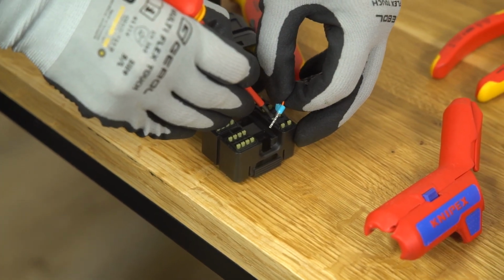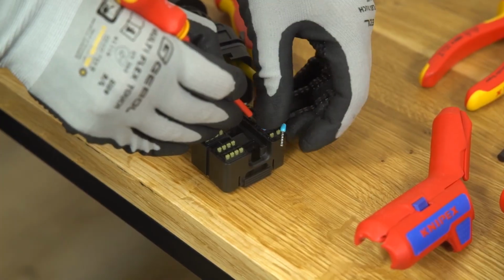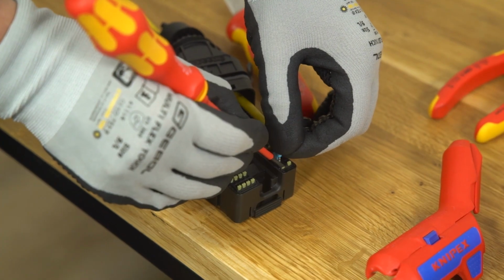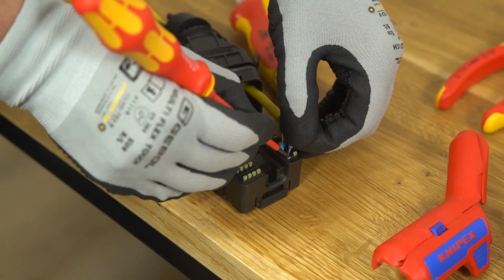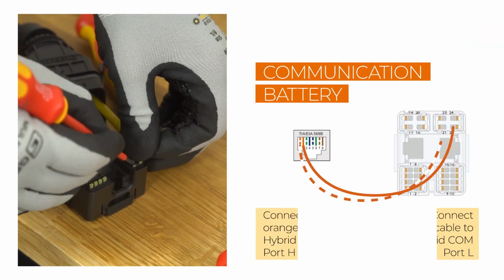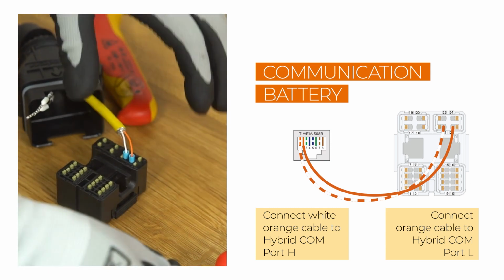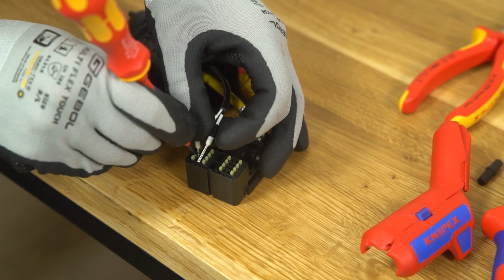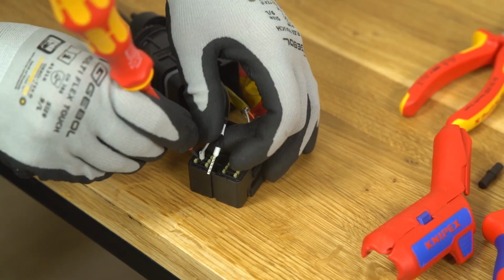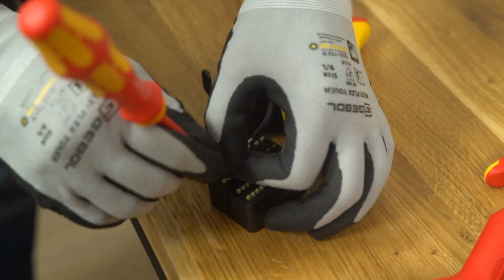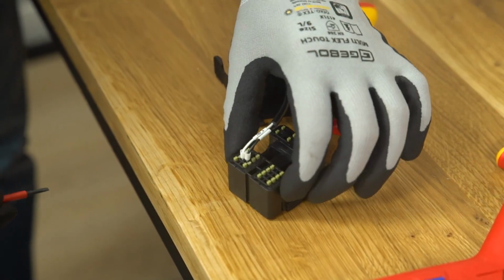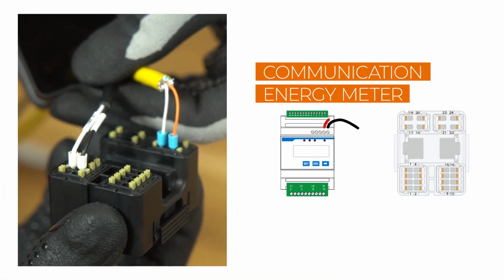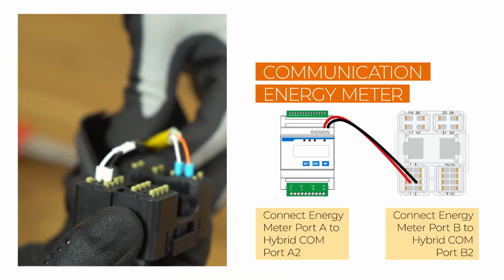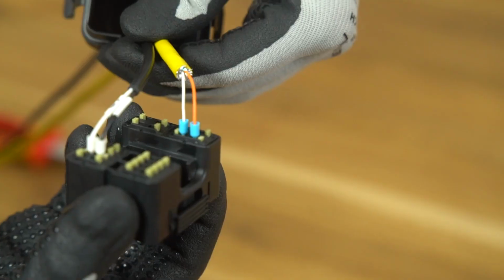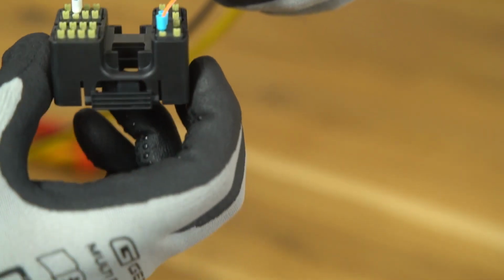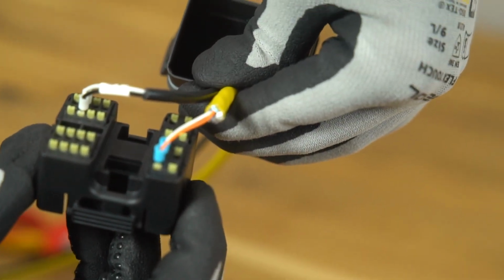The Sungrow battery is connected to the battery terminal BAT on the COM2 terminal when using the RJ45 plug. If you use the pin terminal connection, connect the communication cable to the inverter COM2 ports H and L. To connect the smart energy meter, which is also part of the delivery scope, plug the wires into the A2 port of the COM2 terminal and pin A on the meter and B2 port of the COM2 terminal and pin B on the meter. Check out our energy meter and Sungrow battery installation videos for a detailed step-by-step instruction.